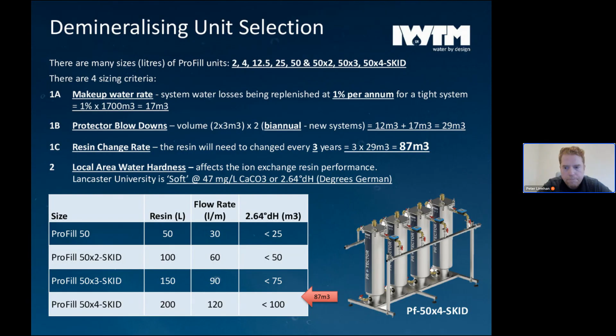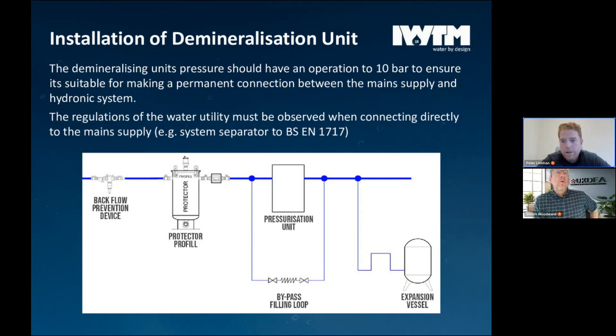But the benefit of having a larger unit, specifically a ProFill 50x4-SKID, is that the flow rate is much higher than if you were to go for a smaller unit. This means you can use this unit to fill the system up with demineralized water, but also in case there's an emergency, or a big leak and you need an emergency fill, you can still use this unit to get the system back up to pressure and full capacity. This is installed before the pressurization unit.